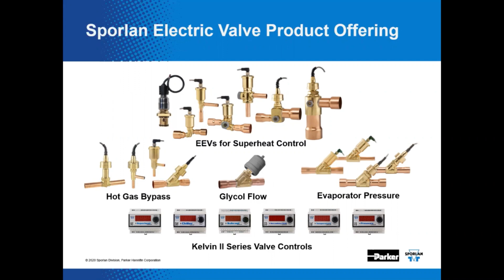There are also specific standalone Kelvin 2 series controllers available to help the package in most cases. These valves have the advantage of being less sensitive to the refrigerant installed in the system and can generally throttle down to lower levels as compared to the mechanical EPR. John, how much lower can they throttle based on their nominal performance ratings, do you think? What would be a good answer? I'm surprised somebody hasn't asked that question.